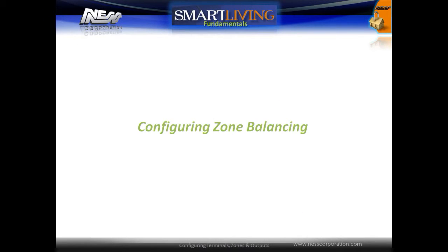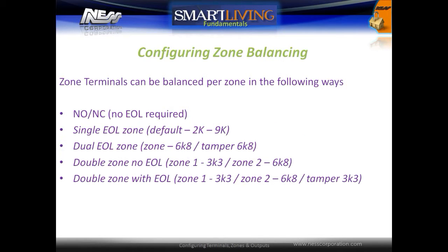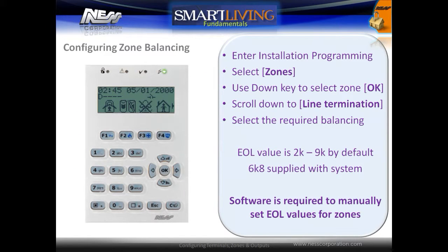Zone terminals can be balanced individually per zone as either: normally open, normally closed with no end-of-line resistor required, single end-of-line, dual end-of-line to provide a tamper circuit, double zone with no end-of-line, or a double zone with end-of-line. By default, zones are configured as single end-of-line and will recognize a value between 2k and 9k.